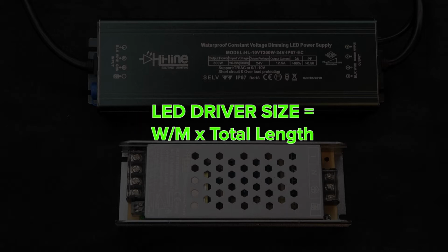Secondly, you will need to calculate the size of the LED driver needed, and that's done by multiplying the wattage per meter of the strip by the total length needed. For example, if your strip is 14.4 watts per meter and you have a total of 10 meters of strip, your driver will need to have a capacity of 144 watts and above.